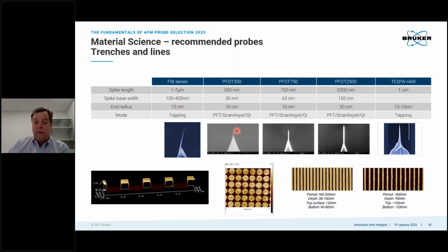And then we have probes that are grown with the electron beam, and they are made at different lengths as well, 350, 750, and 2.5 microns. So these are designed for PeakForce Tapping mode, these 3 here in the middle. We tend to use the FIB probes for tapping. And another nice tapping probe, this is a little more general probe, is the TESPA probe, HAR for high aspect ratio. The spike at the end goes about a micron or 2. I generally expect about a micron or so. And otherwise it performs very similar to a regular tapping probe. And I like this one as well.